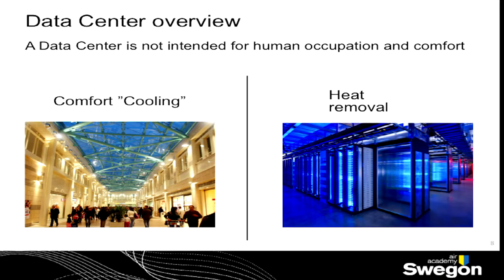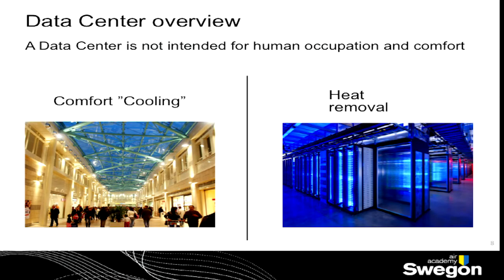I think that it is very important to consider data cooling as an environment completely different from what we are used to with comfort cooling. If we consider comfort cooling, we have to create a stable condition for human beings, okay, with humidity and temperature. Instead, in a data center, the only thing we have to do is to remove the heat generated inside. We don't have to take care about anything else. A data center is not an ambient for human beings, so the only trouble that we have to afford is the heat removal, only this. Forget about all the other stuff, because sometimes some mistakes are committed by considering these two ambients as not so different as they are.